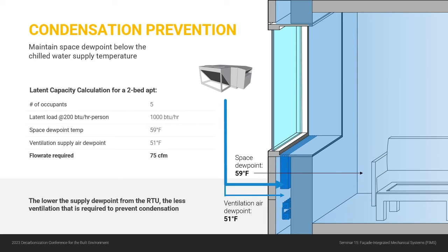So it's probably your dehumidification that's going to drive your ventilation sizing instead of the code requirement, which in many ways is a good thing because that's good for indoor air quality. It's nice to go above and beyond the code requirement. In this example, I use 51-degree dew point. If you dry it out more than that, you can reduce the amount of air you need. So you can do it with conventional vapor compression cycles, but if you start thinking about using things like desiccants to really dry out that air, then you can really bring down the amount of air that you need.